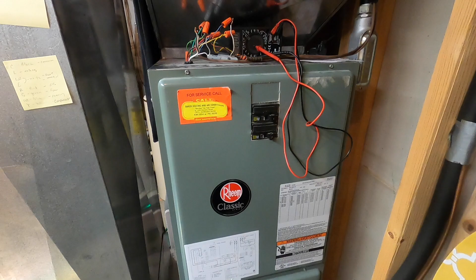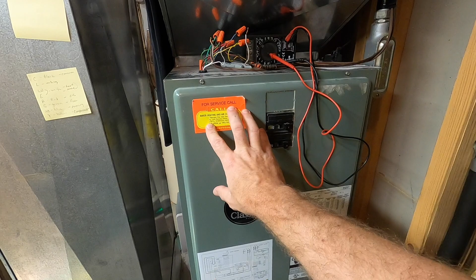All right, so here we are at the air handler. Obviously this has the auxiliary heat unit inside of it. There's several electric elements there that come on when the heat pump can't handle the temperature. You know, some people have natural gas. We have all electric, so there's electric heating elements in there. So we know that somewhere in either the control board in here, the control board at the thermostat, or the control board outside, is telling the electric heat to come on.